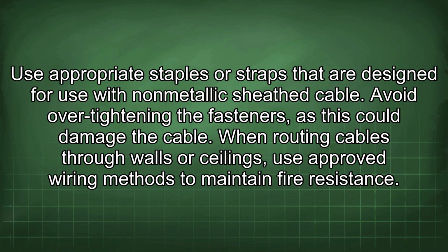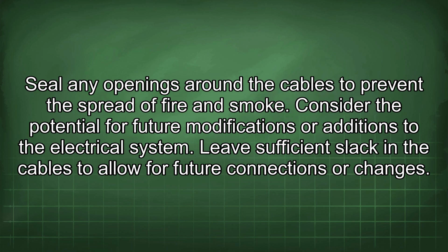When routing cables through walls or ceilings, use approved wiring methods to maintain fire resistance. Seal any openings around the cables to prevent the spread of fire and smoke. Consider the potential for future modifications or additions to the electrical system. Leave sufficient slack in the cables to allow for future connections or changes.